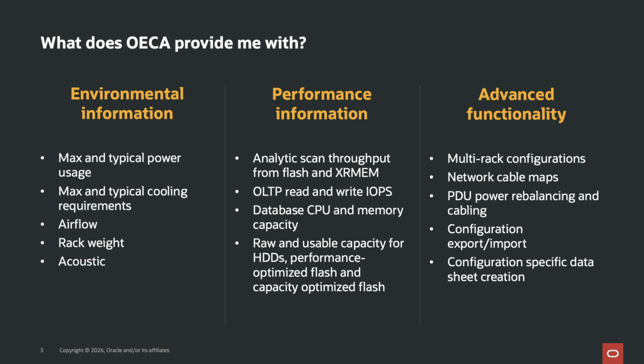So what does OECA provide me with? Well, OECA provides a lot of really useful information to help you integrate Exadata into your data center. It gives you environmental information, including max and typical power usage for the configuration you've modeled, max and typical cooling requirements, airflow, rack weight, and acoustic information.